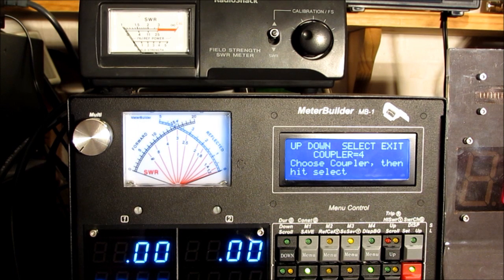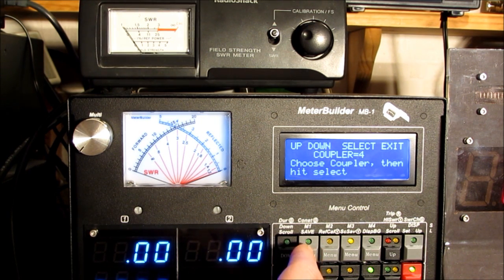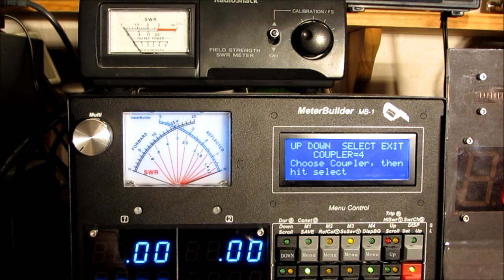The first thing I have to do on this screen is select the coupler port we're calibrating. You have to use caution here, since you don't want to erase or overwrite the wrong coupler. You can use the up or down button to select coupler 1 through 4. Coupler 4 was selected, so we were all set up, but the important point is to make sure the coupler you're interested in editing or doing a new calibration on is indeed the correct one.